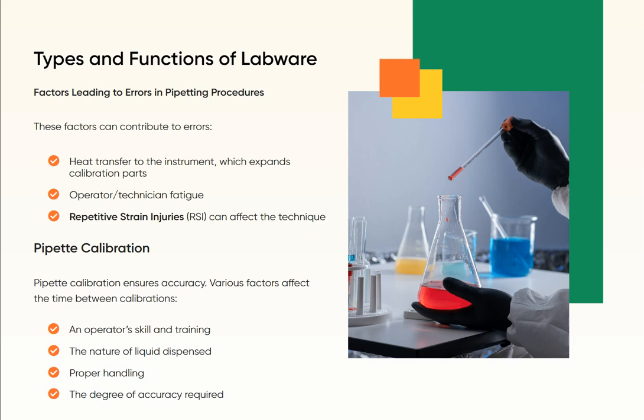Pipette calibration ensures accuracy. Various factors affect the time between calibrations, including an operator's skill and training, the nature of the liquid dispensed, proper handling, and the degree of accuracy required.